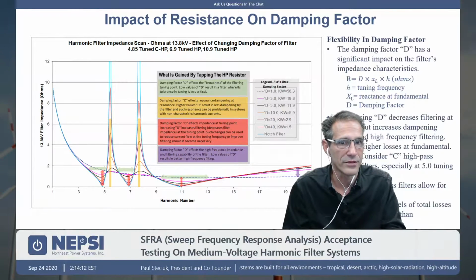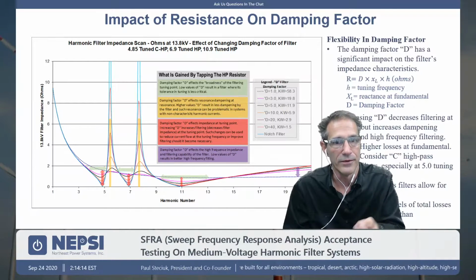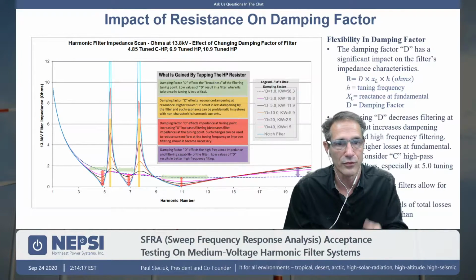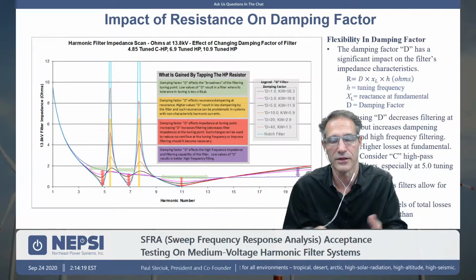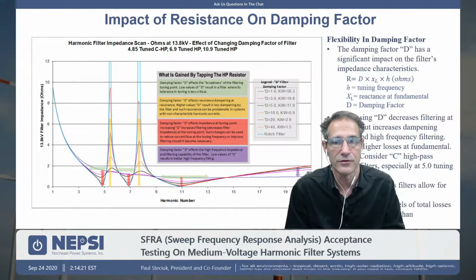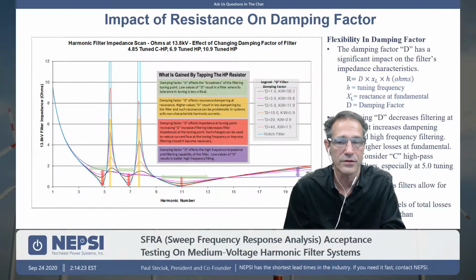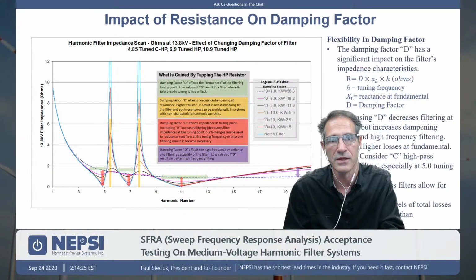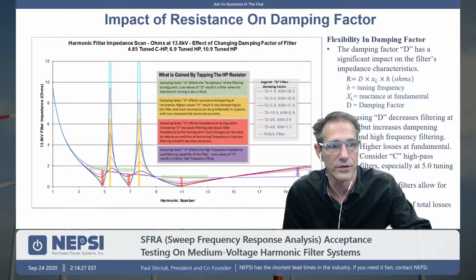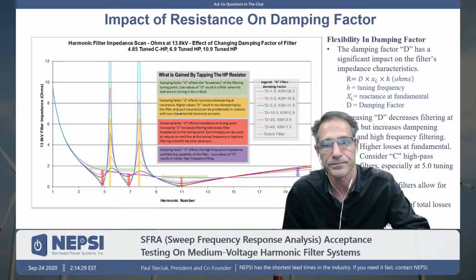And the way we do a hot resistance value is we have to dub in, basically insert some impedance or resistance into the circuit to create this other profile. So we end up with two test results, a cold resistance test and a hot resistance test. So this is the impact of resistance on the system.